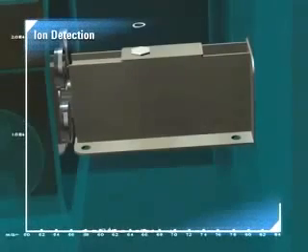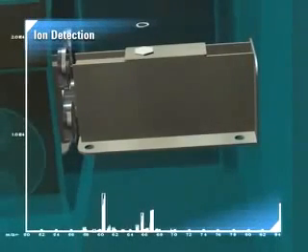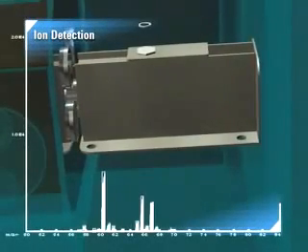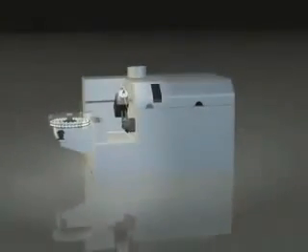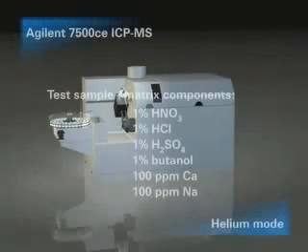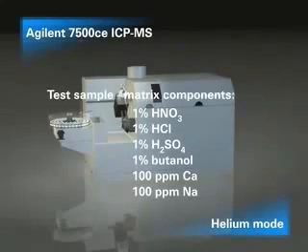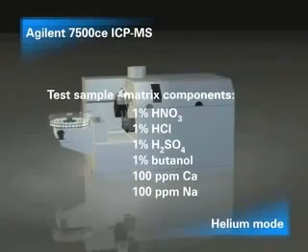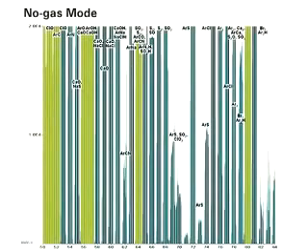Ions strike the detector and the resulting electronic signals are processed by the detector electronics and stored in a multi-channel scaler, creating a mass spectrum where intensity at a given mass is proportional to the concentration of the isotope at that mass. To illustrate the interference removal power of the helium mode, a very challenging sample matrix containing these components was analyzed. Spectra were obtained for the mid-mass range where most polyatomic interferences occur. This spectrum shows the matrix interferences that occur in normal ICP-MS.